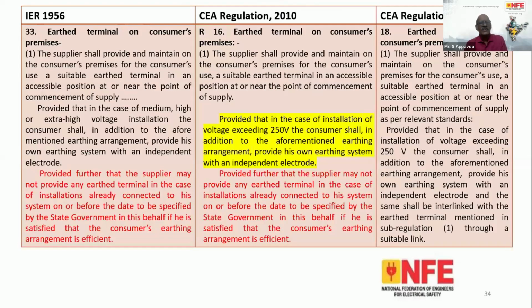So coming to the supplier's part again, we have had regulations since 1956. Now I am coming to regulation 18 of 2023. It insists that suppliers shall provide and maintain, at consumer premises, an earthed terminal in an accessible position. Why? For the use of consumers. So this is nothing but a TN-S. It is from the year 1956 onwards. But unfortunately, most of the domestic premises and the LT premises are not abiding by this because of the flaws that will be explained in the subsequent slides.